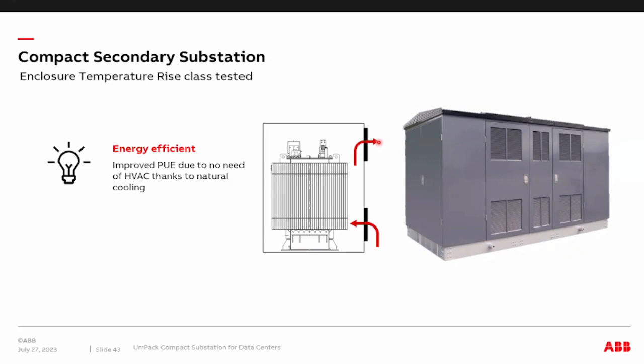So if we are able to eliminate all the mechanical ventilation or ACMV equipment that caters to these substation equipment, that will actually lower down the PUE, compared to conventional substation where we will be having a typical ACMV system that will require power supply, which will actually increase the PUE of the whole data center. That can be eliminated with this type of solution.